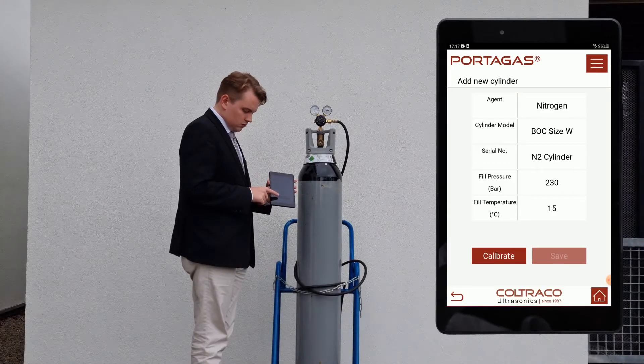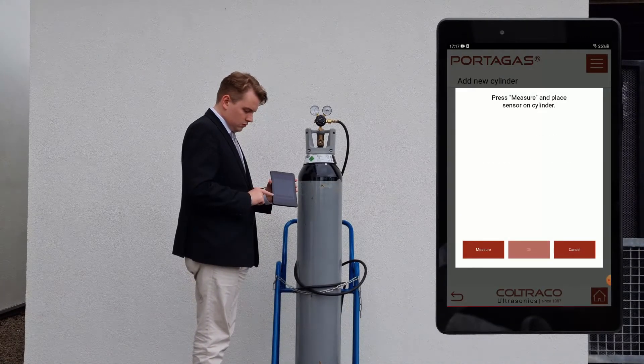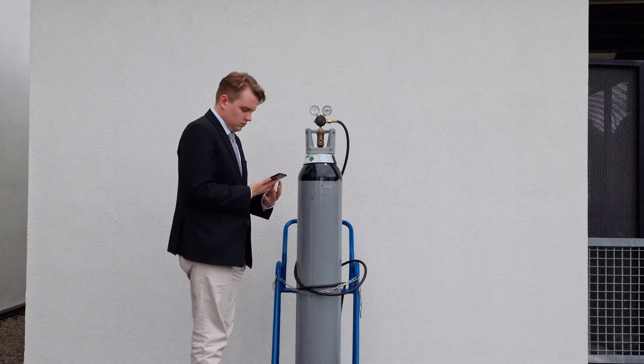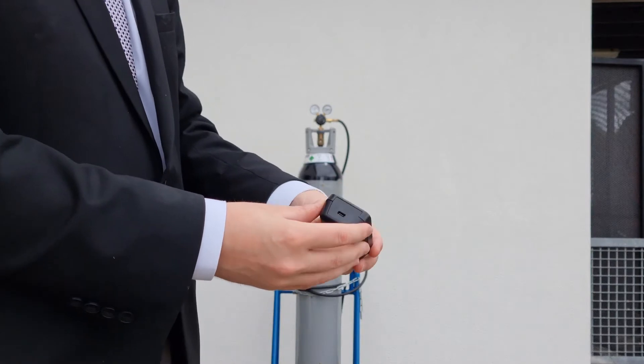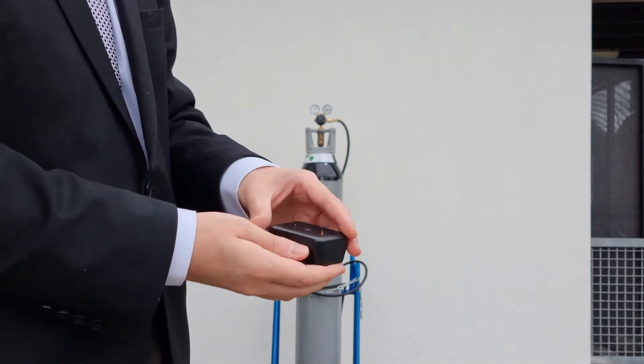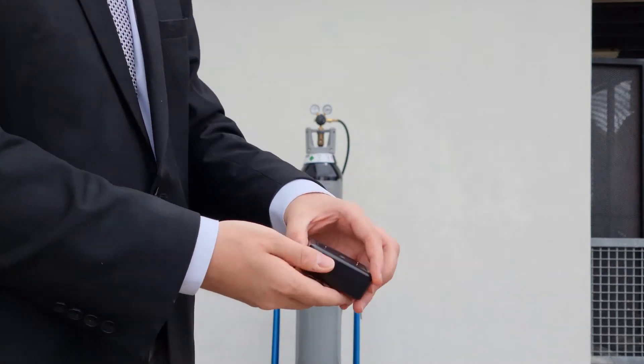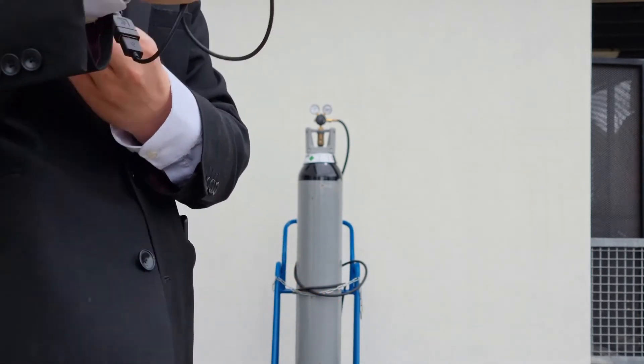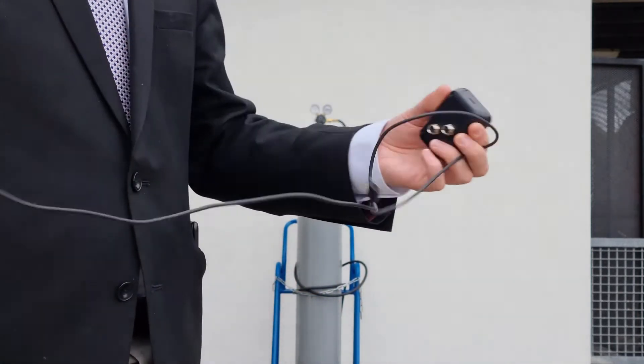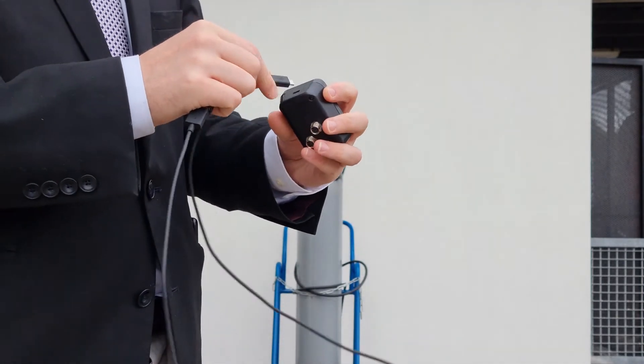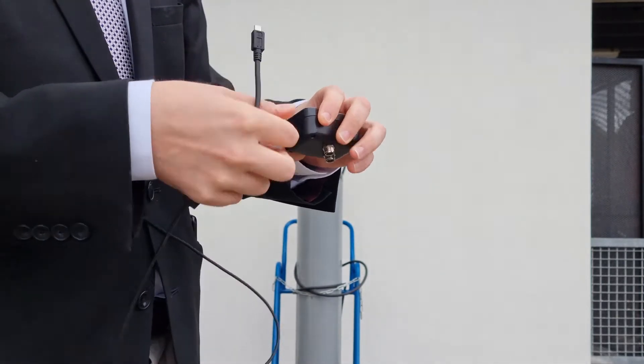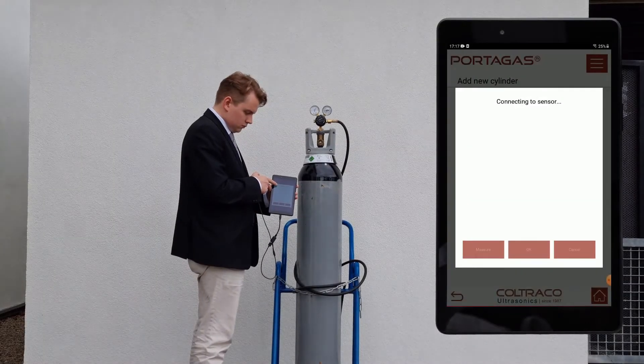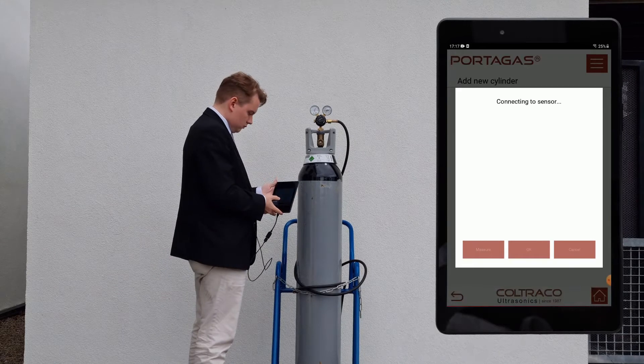Angus presses Calibrate to calibrate the instrument to the cylinder. To do this, he attaches the sensor to the tablet using the USB cable provided. He then presses Measure and places the sensor on the cylinder as instructed.